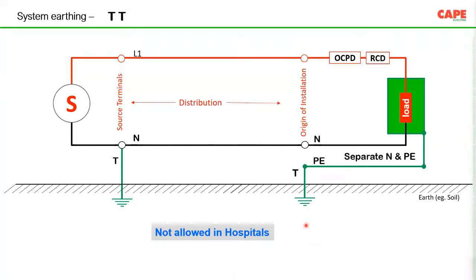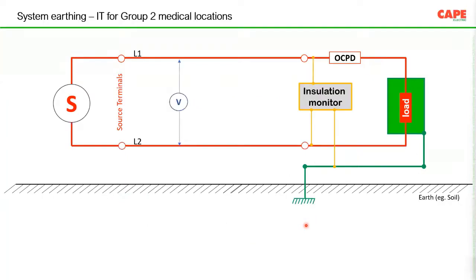It looks like a TT system, but practically, in my experience, in hospitals following this kind of system, each and every part of the electrical installation, such as some of the biomedical equipment, sometimes the isolation transformer, sometimes the UPS, sometimes electrical DBs, and each of the transformer and DG, has 2 earths for neutral and 2 for body. Such a system is actually not allowed in hospitals, and it is completely wrong. We are supposed to follow a proper TN-S system.